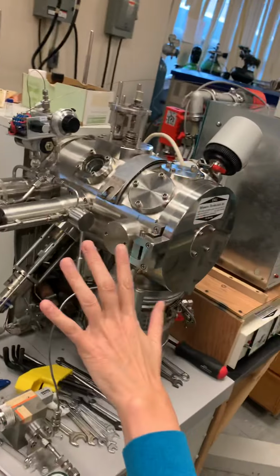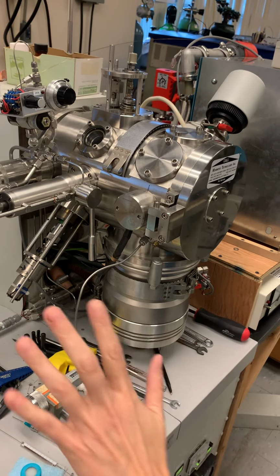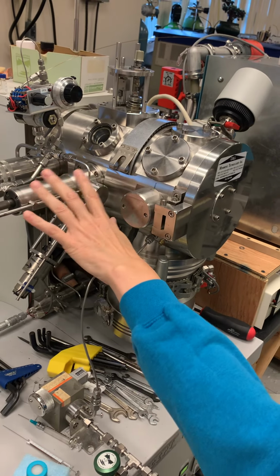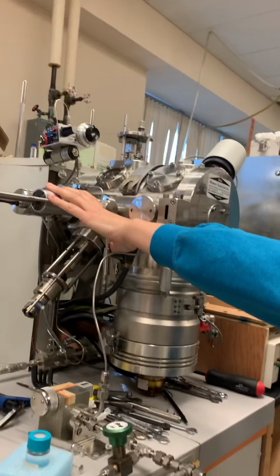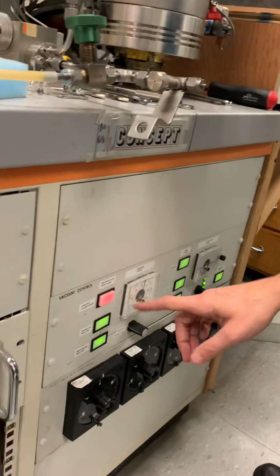So now the contrast between here and here is lessened. I'm not at atmosphere opening up the gate valve. I won't break the ion gauge. I will not break the filament on my source. So now I'm going to very carefully open up by keeping an eye on this gauge at the same time.